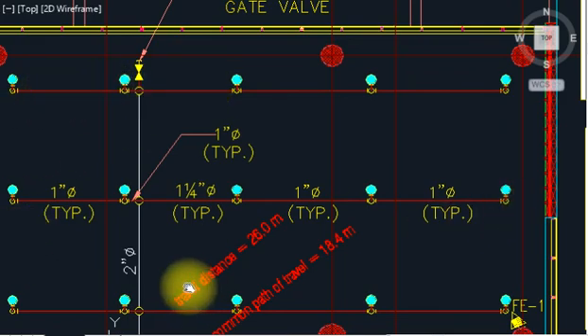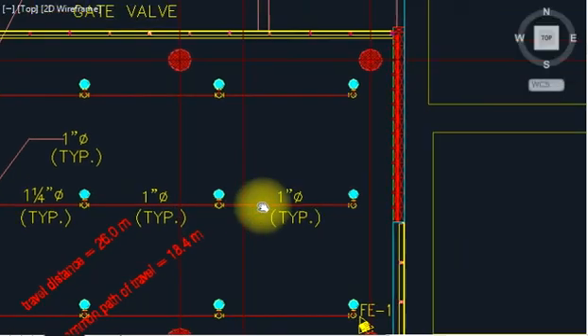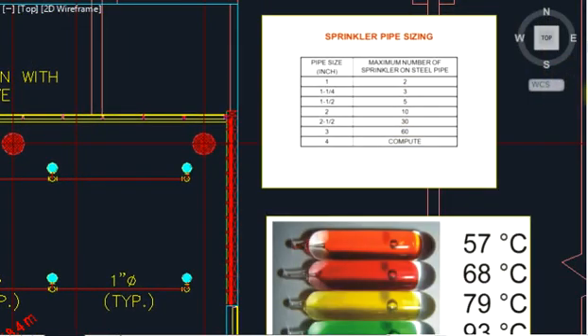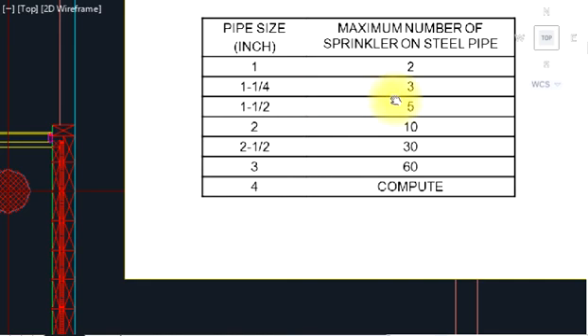When you have 10 sprinklers, you need a 2 inch pipe (50mm). As per NFPA, the distribution follows this chart: 1 inch = 2 sprinklers, 1 and 1/4 inch = 3 sprinklers, 1 and 1/2 inch = 5 sprinklers, 2 inches = 10 sprinklers. The pipes used are black steel schedule 40 or 80 — seamless or sometimes non-seamless — which is a grooved or screwed steel pipe.